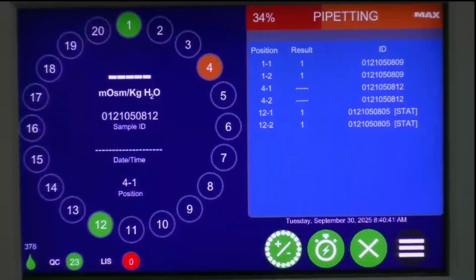But if you want to move forward with the new lot, then you can go ahead and move forward with that, and you won't need to perform enzymatic cleaning anymore either. Okay, so from your experience, what's the number one tip for keeping this instrument running smoothly? I would say use a fresh vial of Clinitrol 290 every morning. You don't want to have any issues with QC drift due to evaporation.